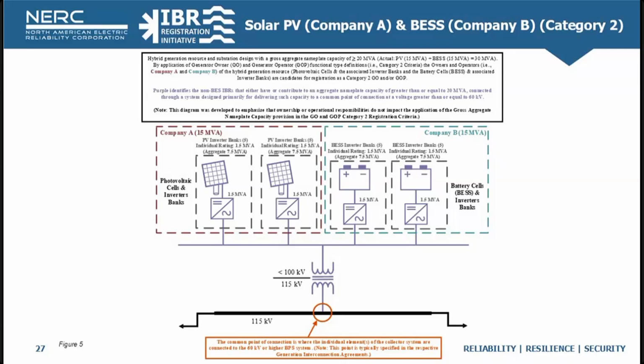The common point of connection, again in the orange circle, is at a voltage of 115 kV, which exceeds the 60 kV threshold. So here identified in purple are the facilities that meet the Category 2 criteria. And as a result, the owner of Company A, the solar generation resource, and the owner of Company B, the battery energy storage generation resource, are candidates for registration as Category 2 GOs, and the operator is a candidate for registration as a Category 2 GOP.